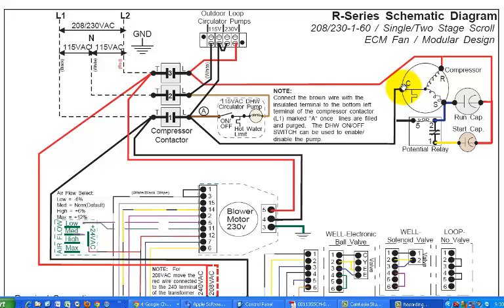So what we need to have for that compressor to operate is that potential voltage difference. We would be able to measure across between those 2 points. They are actually buried a little bit in terms of the contacts, but theoretically we could measure across those 2 points, and if we don't see that 230 or 240 or thereabouts voltage, we would know that there's some issue about the voltage getting to it, and the compressor simply would not work. It's not going to happen.